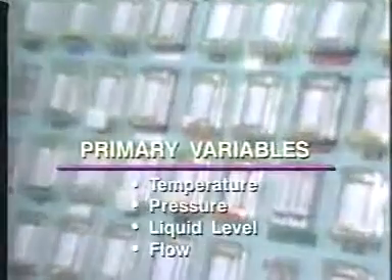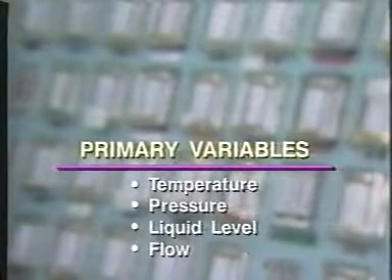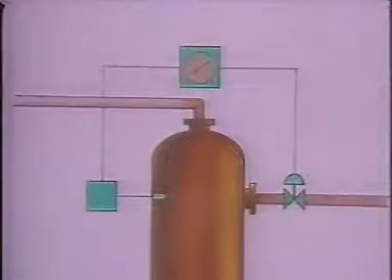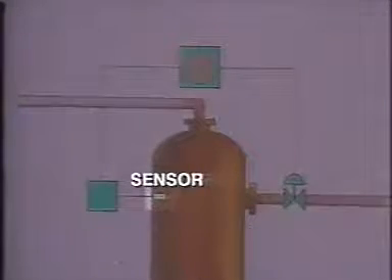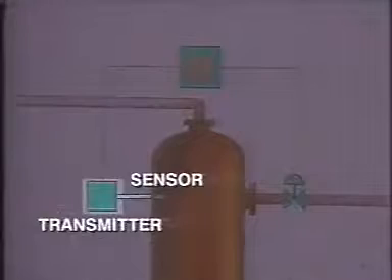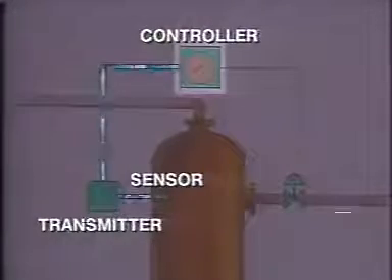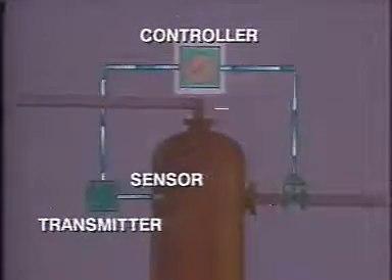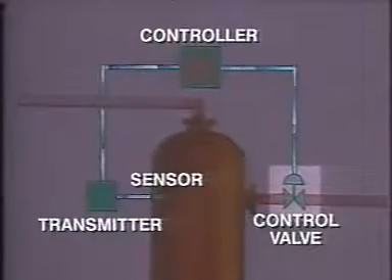There are four major variables or process conditions that must be controlled in any distillation process: temperature, pressure, liquid level, and flow. Suppose we want to control the temperature at the top of a distillation column. The first thing we need is a measuring instrument that can sense the temperature. Next, a transmitter interprets this measurement information and sends a signal to a controller. The controller is programmed to maintain tower top temperature at a desired value called set point. If the temperature has deviated from set point, the controller sends a signal to a valve telling it either to open or close. This changes the reflux rate to the top of the tower and brings the temperature back to set point.